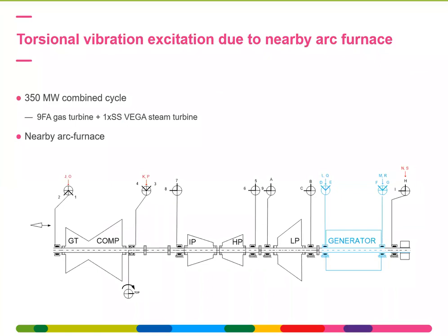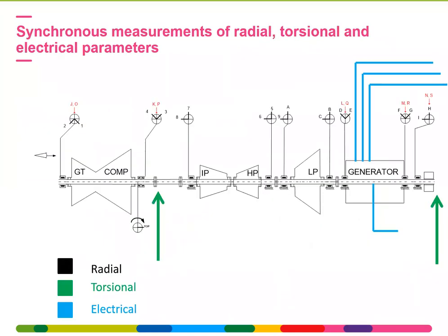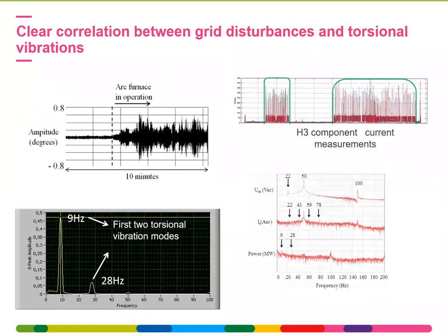A last example is a nearby arc furnace, which was disturbing the shaft line. Electrical, torsional, and radial vibration measurements were made, as you can see. And here you can see the results. The torsional natural frequencies on the bottom left picture are at 9 and 28 hertz. These are excited as soon as the arc furnace is in operation, as you can see on the top left picture. This is really steady state operation.